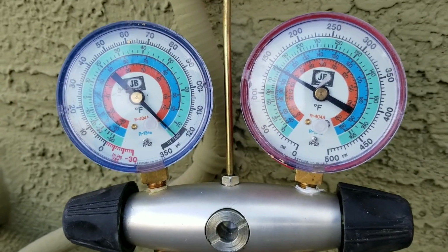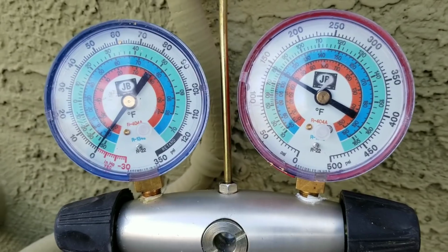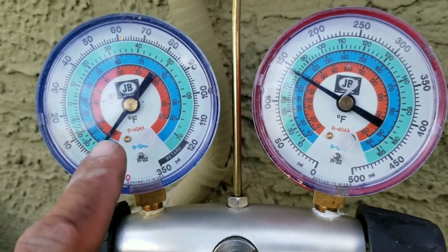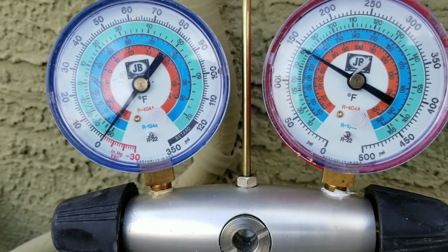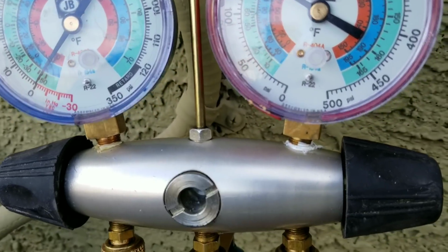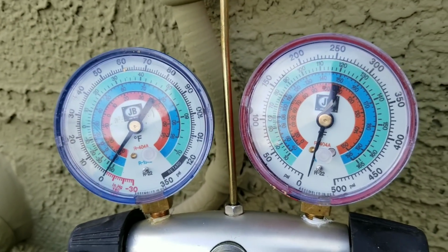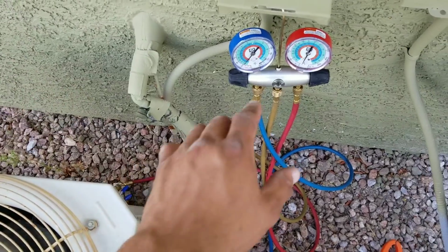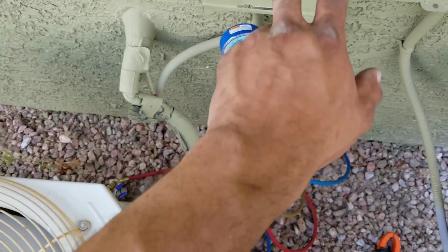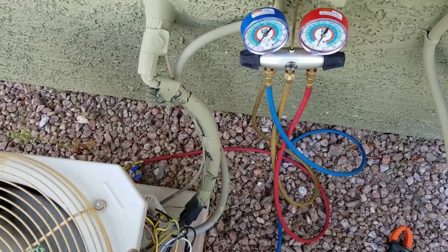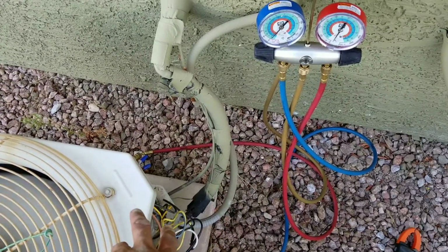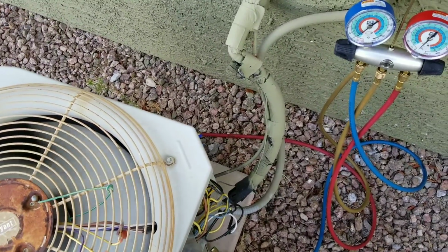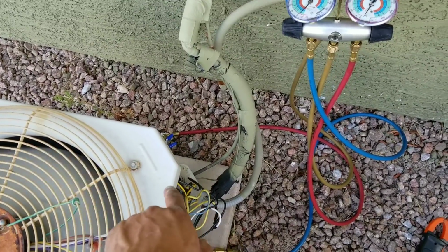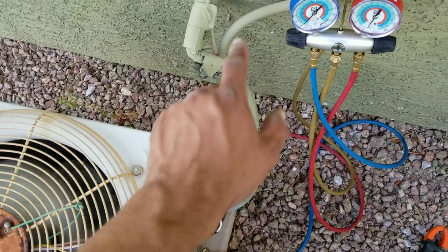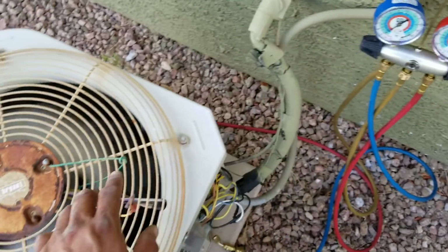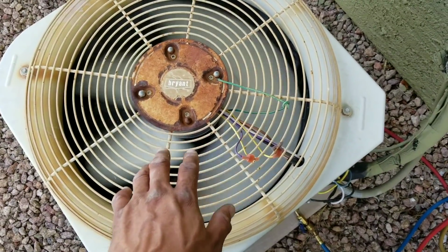I'm going to remove my low side, and you can see that I have no pressure right now. I'm going to remove my high side. Right now I know I have refrigerant in the system. I know I have 240 volts going to my condensing unit. I do have 240 volts going back to my compressor. I do have 24 volts, the low voltage, engaging from my thermostat when it's calling for cool, and right now my fan motor is running.